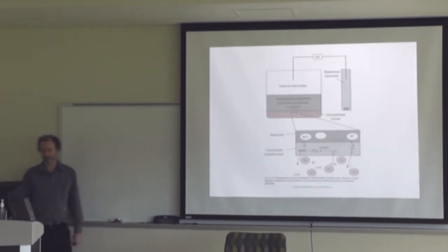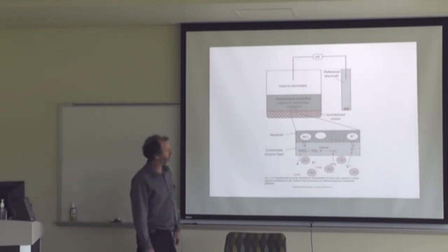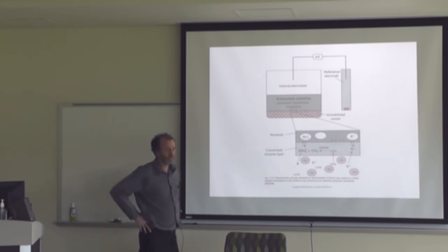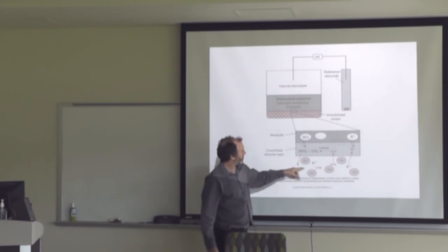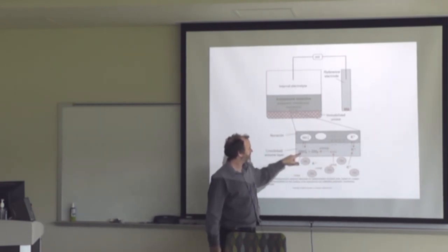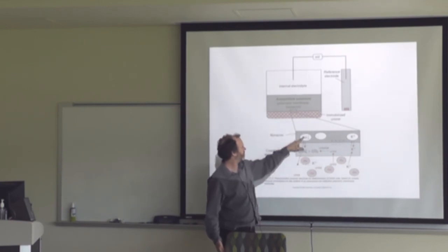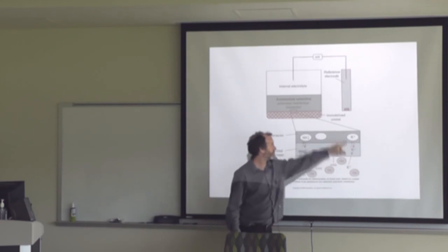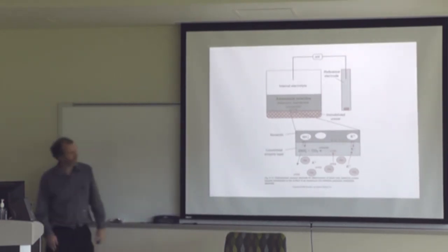And this shows you the ammonium selective membrane again. And this is another enzyme-related sensor where you're measuring ammonium concentrations, or urea basically. You measure urea. Urease is in there, which creates ammonia and carbon dioxide. The ammonium diffuses across a membrane, generating that current in exchange for potassium.